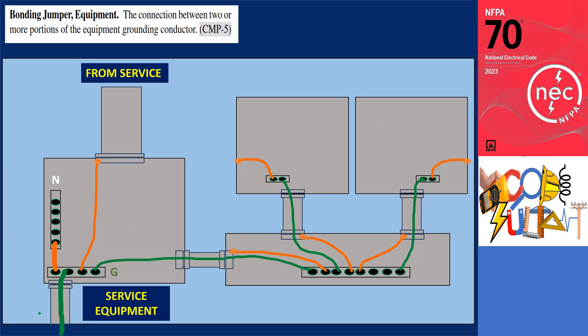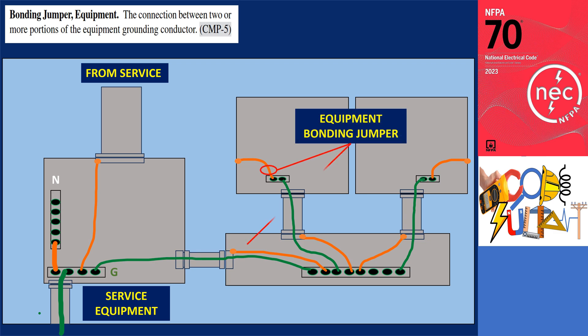An equipment bonding jumper refers to the connection between two or more sections of the equipment grounding conductor. These bonding connections are made between different portions of the equipment grounding system. For example, the bonding between metal raceways, the grounding bus terminal, and the panelboard enclosure bonding would be classified as an equipment bonding jumper.